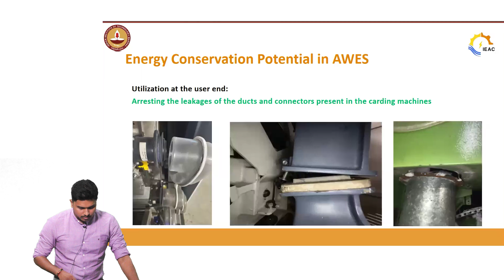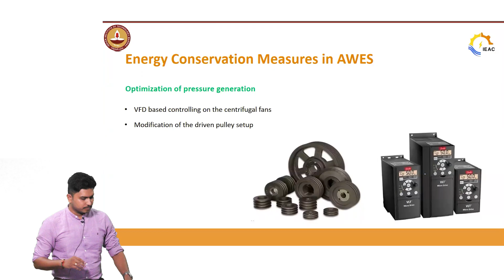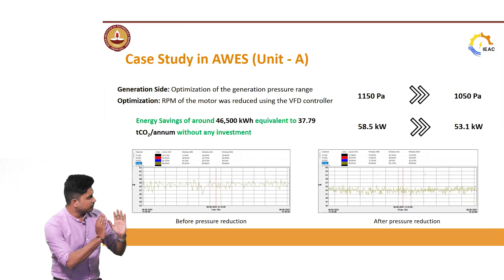So one way of conserving energy is to use variable frequency drives. With these variable frequency drives, you can use any pulley to do your operation, but the variable frequency drive will provide you the right amount of torque and right amount of speed so that it can produce the necessary amount of energy. So this is an example: from the generation side, you are producing 1150 pascals. If you reduce it to 1050 pascals, the energy savings corresponding to that will be as follows: 58.5 kilowatts is used initially, but after changing from a normal motor to a VFD motor, you go to 53 kilowatts. So this is translating into your energy conservation.